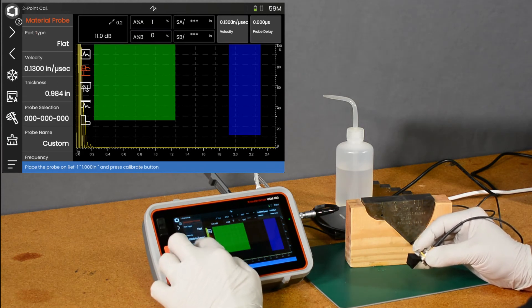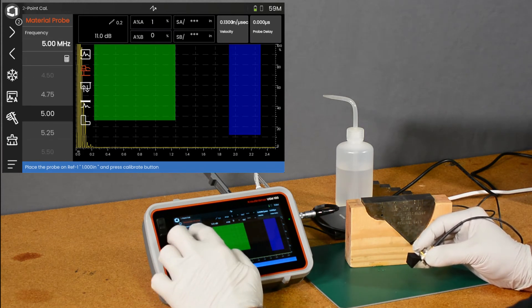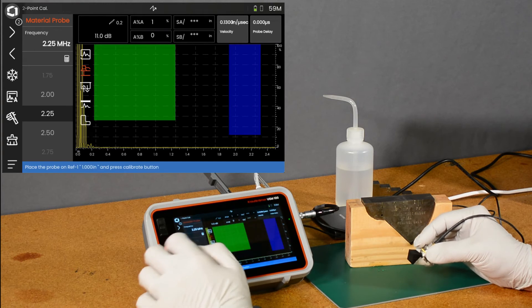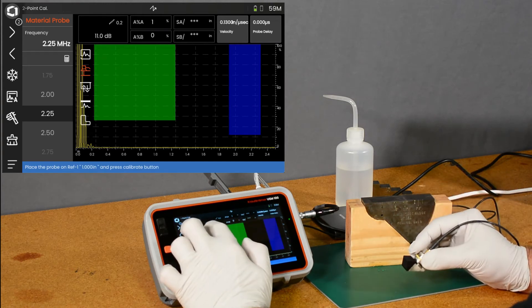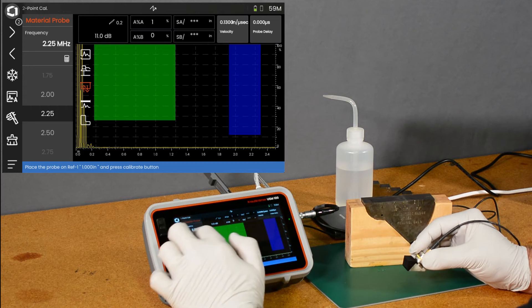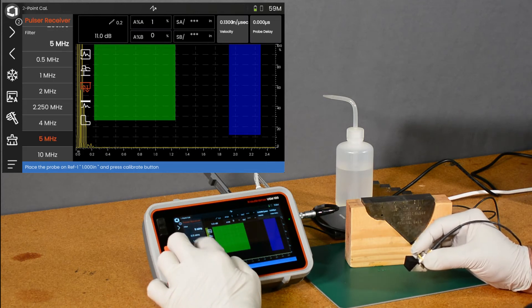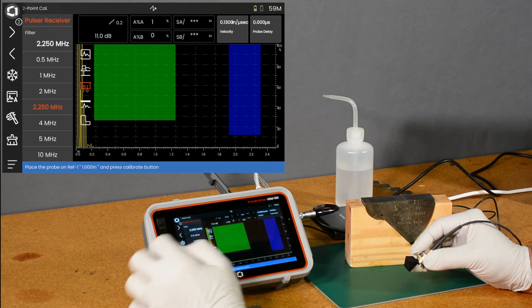Let's take a look at our probe frequency. We'll set that to 2.25 to better optimize the pulser for this probe. And we're going to go to the pulser receiver menu, and we'll change our filter to two and a quarter megahertz.